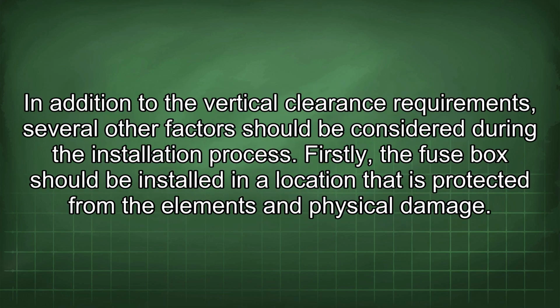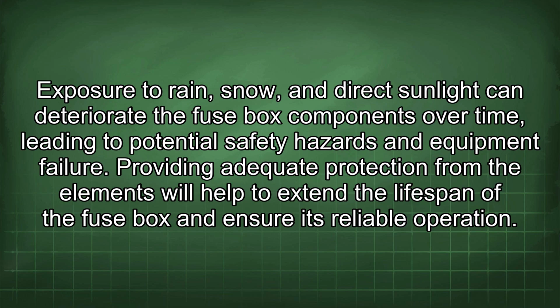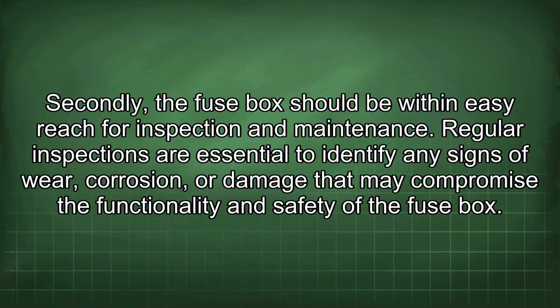In addition to the vertical clearance requirements, several other factors should be considered during the installation process. Firstly, the fuse box should be installed in a location that is protected from the elements and physical damage. Exposure to rain, snow, and direct sunlight can deteriorate the fuse box components over time, leading to potential safety hazards and equipment failure. Providing adequate protection from the elements will help to extend the lifespan of the fuse box and ensure its reliable operation. Secondly, the fuse box should be within easy reach for inspection and maintenance.